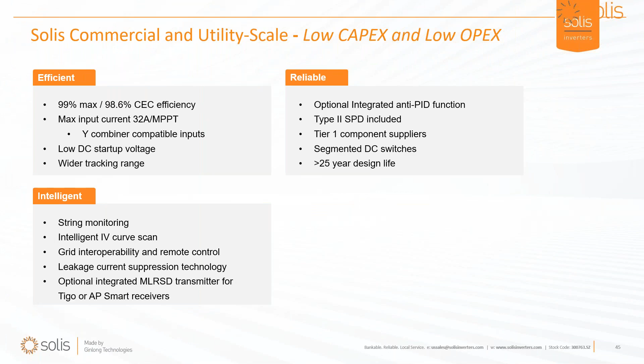So what that ends up being is you really start closing the gap with the CapEx cost of string inverters with the new central inverters. You know, at this level, you're not really using MLPE. It's really a game between the centrals and the string inverters. And really, it's with these new string inverters and their new capability to not have a fire drill every time the inverter goes down. It's only a segment of the system that's down, and you can do your monthly service calls on these big systems and keep your OpEx costs low. New IV curve scanning that you can do remotely.